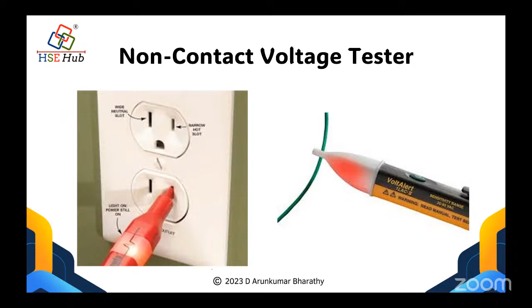Where they will use this tester in a regular manner, because for a grid and bus bar, it will carry an induction up to 4 or 5 feet. So reaching into the induction area will be unsafe for a person. That's why they use this yellow colored hot stick, and they use the non-contact voltage tester only to check the presence of voltage.